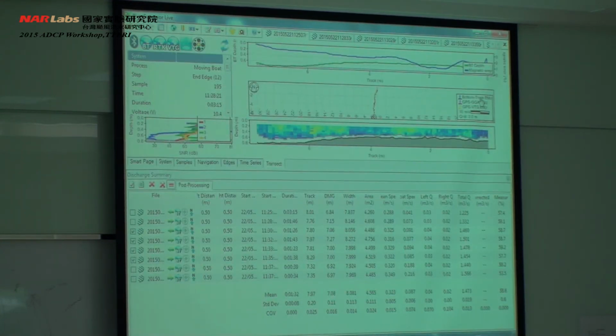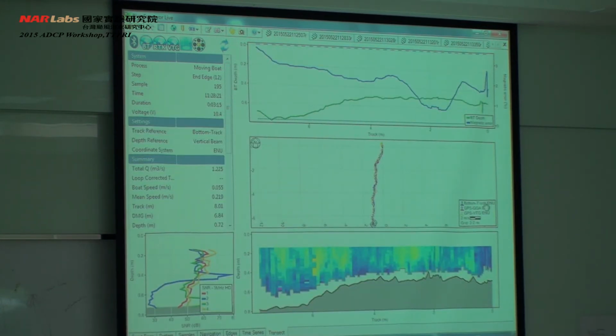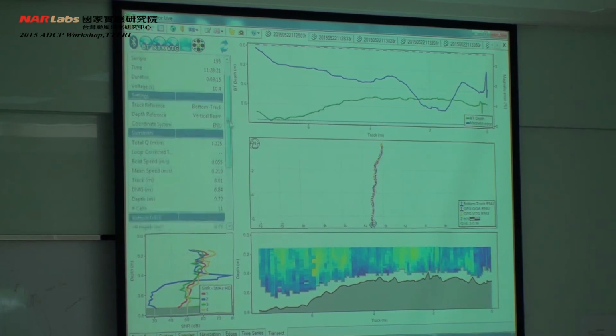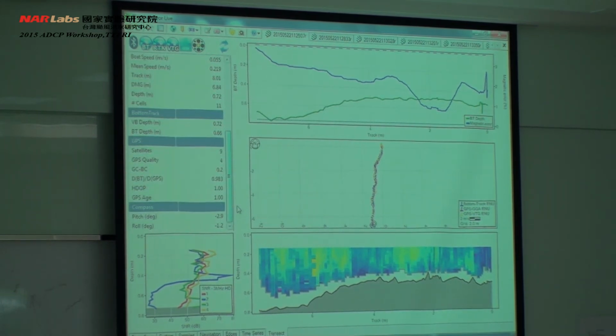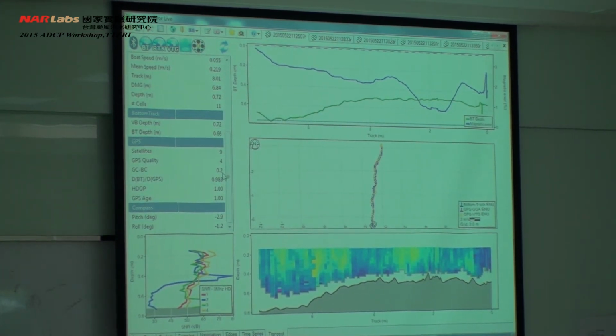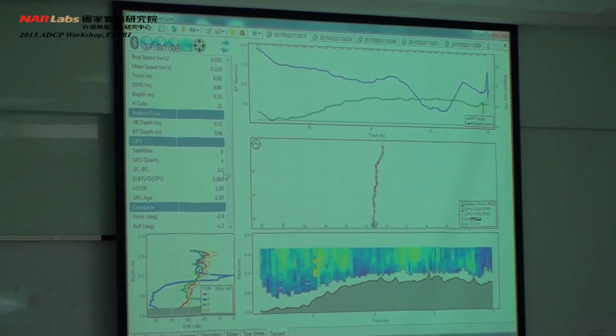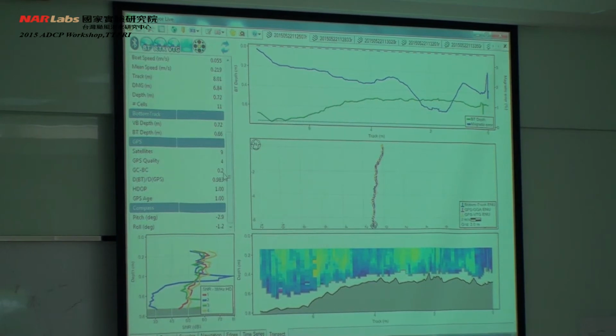I have a question about how to change the angle. So we don't need to change it on this one, because this was all okay. But if I wanted to change it, I would go down to the bottom here with the GPS. I would look at the GPS ports, GC to BC, and it says there's 0.2 of a degree difference. It's nothing. It's well inside the 2 degrees that is the specification of the unit.